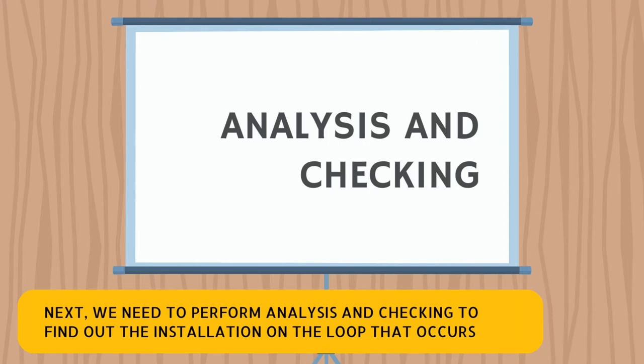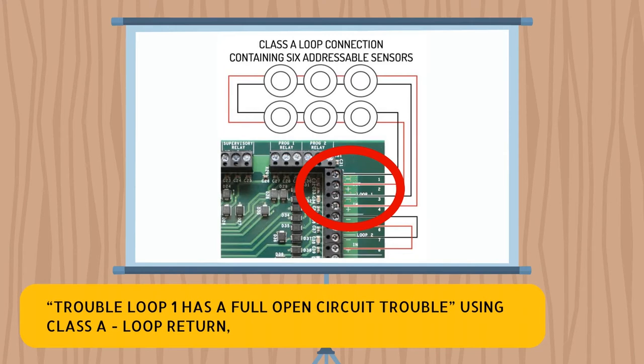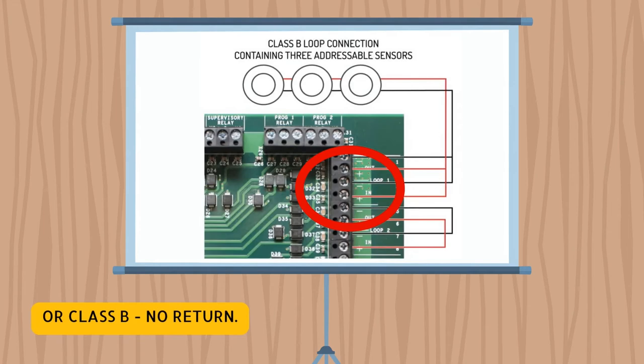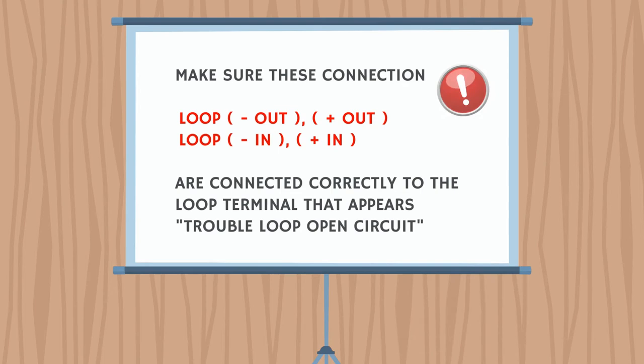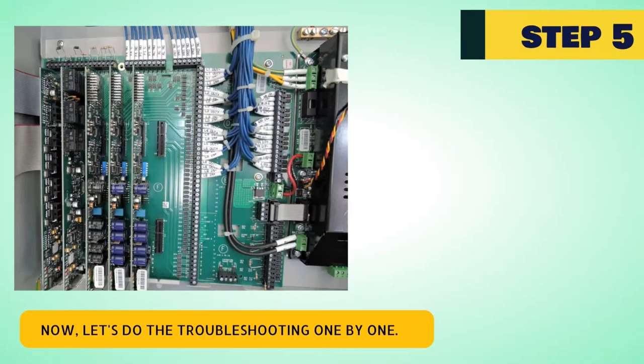Next, we need to perform analysis and checking to find out the installation on the loop that has the fault. Trouble loop 1 has a full open circuit trouble — using class A, loop return, or class B, no return. Make sure these connections are connected correctly to the loop terminal that shows the trouble loop open circuit. Now, let's do the troubleshooting one by one.